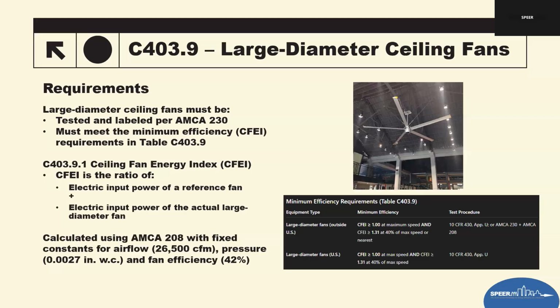Confirm labeling matches the AMCA 230 requirements. And then review whether the project location uses U.S. or non-U.S. requirements. That's probably going to be not applicable for that. And then field inspection considerations. Physical fans should be labeled as tested. And then installed fans must match the approved model number, so verifying what was on plan review actually matches what was installed. And then some jurisdictions may also require spot checks of speed control settings as well.